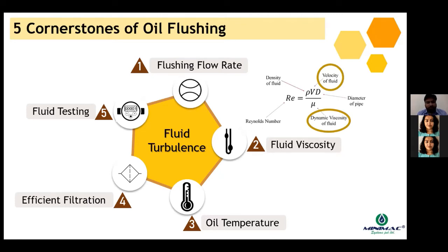The second cornerstone for oil flushing is fluid viscosity. We all know that when the fluid viscosity goes down, the Reynolds number would be much better. And hence, we need to have a lower fluid viscosity so that we can develop a better flushing flow rate and we can have a better Reynolds number or a better turbulence in the pipeline. The third one is oil temperature. The fourth is efficient filtration. And the fifth one is fluid testing. So we would be capturing all these 5 cornerstones over the next 5 slides.